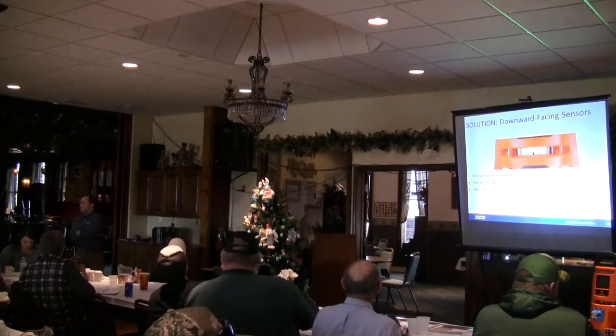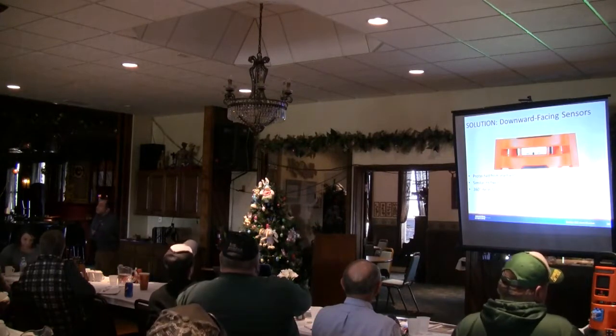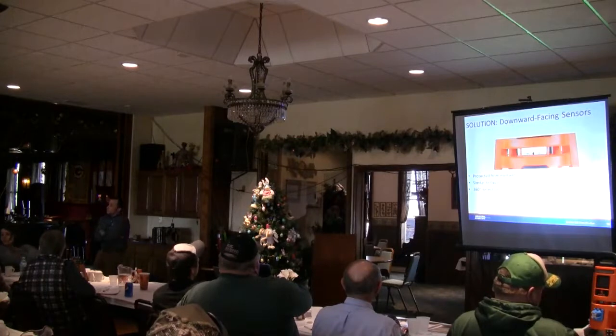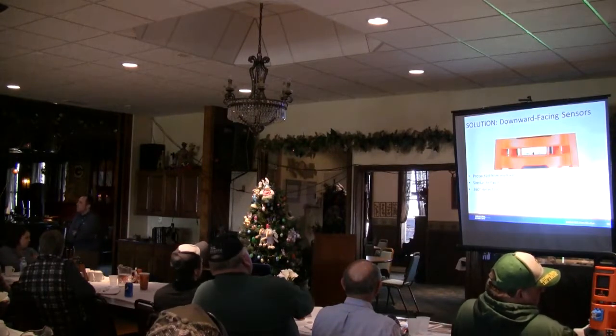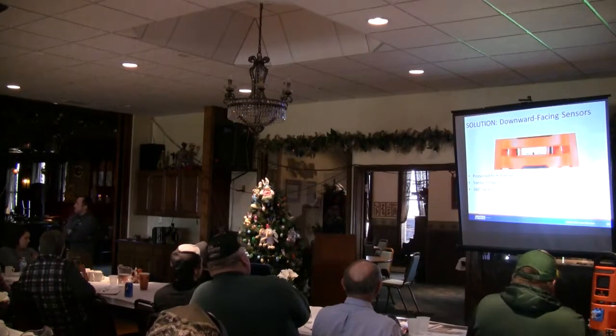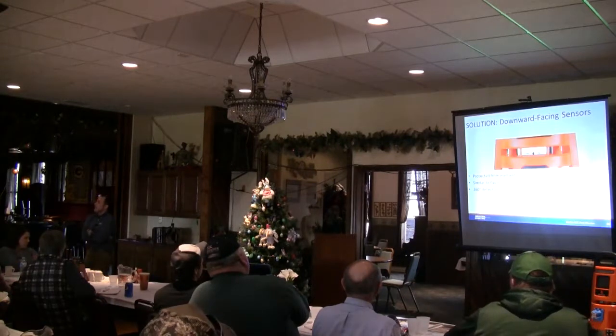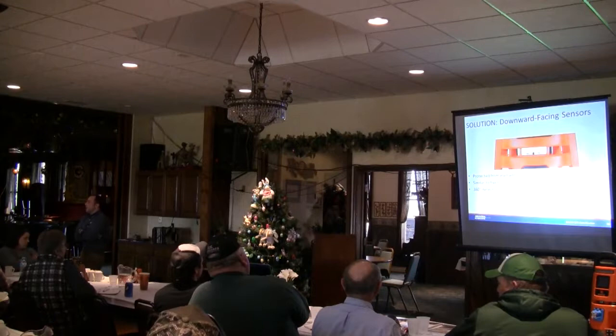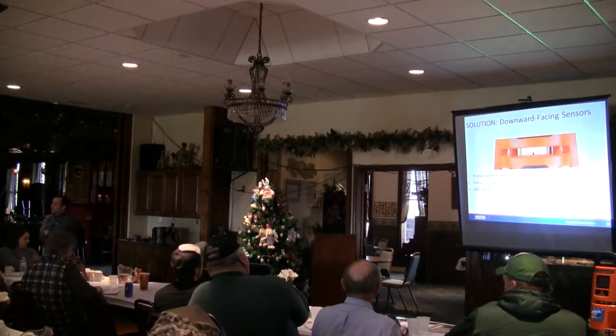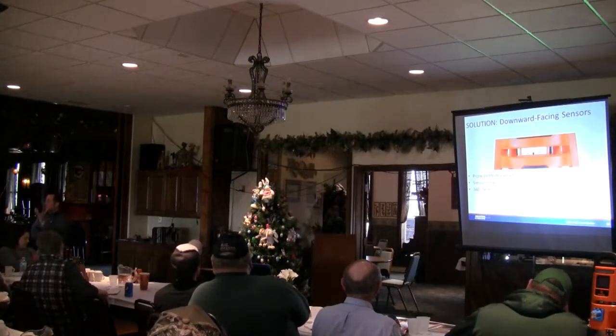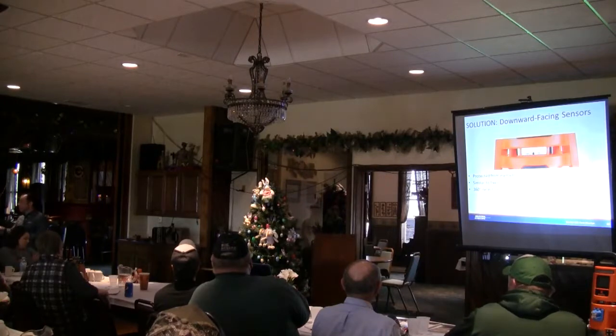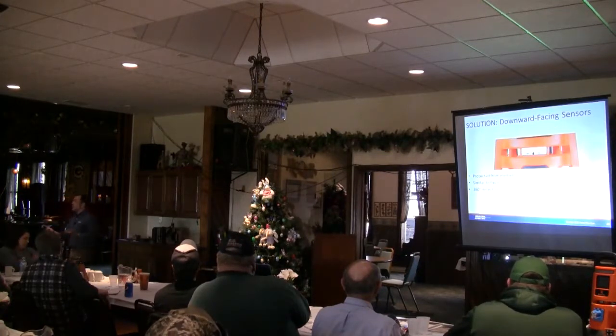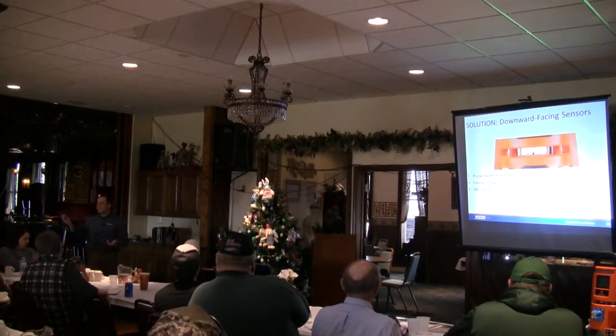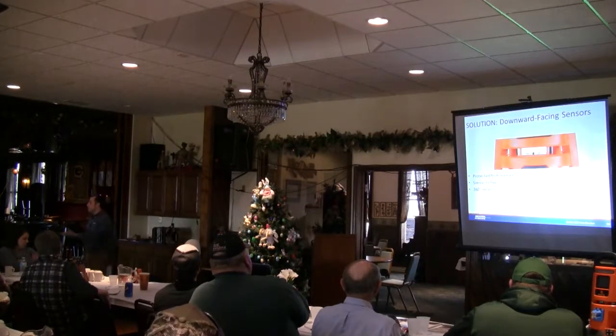Those devices also use different sensing technology. The really inexpensive ones use different sensing technology, closer to solid state sensor technology, which is not as fast to respond and not as accurate. So that's why your CO detector in your house that you have on the ceiling is different than these, because they work a lot differently, right? They both detect CO, but this is night and day different than that. The technology is different. But I would agree with what you're saying.